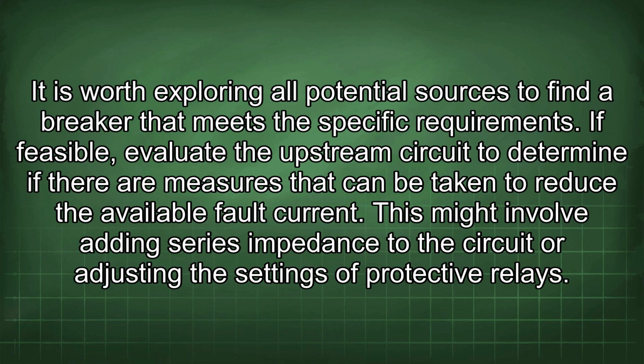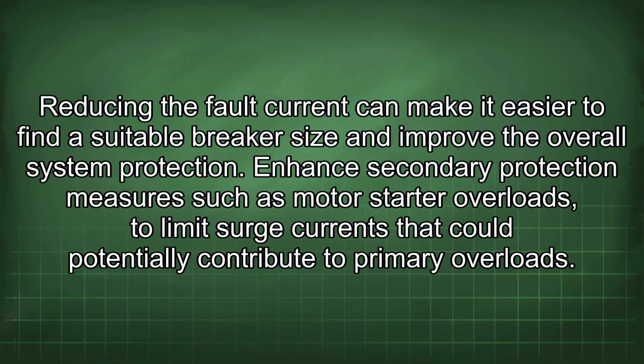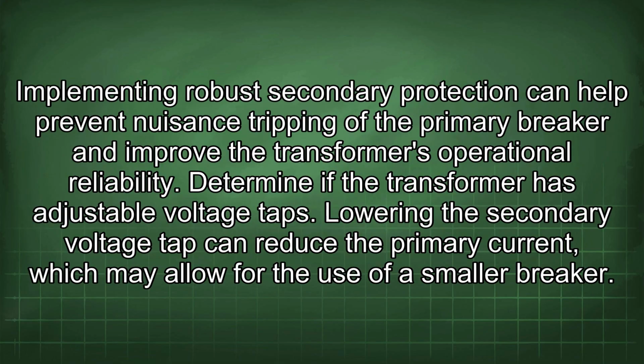If feasible, evaluate the upstream circuit to determine if there are measures that can be taken to reduce the available fault current. This might involve adding series impedance to the circuit or adjusting the settings of protective relays. Reducing the fault current can make it easier to find a suitable breaker size and improve the overall system protection. Enhance secondary protection measures such as motor starter overloads to limit surge currents that could potentially contribute to primary overloads. Implementing robust secondary protection can help prevent fuse tripping or nuisance tripping of the primary breaker and improve the transformer's operational reliability.